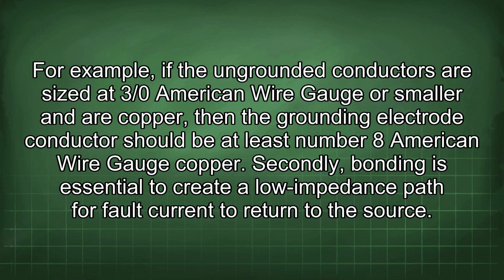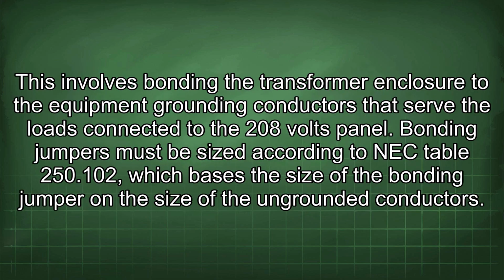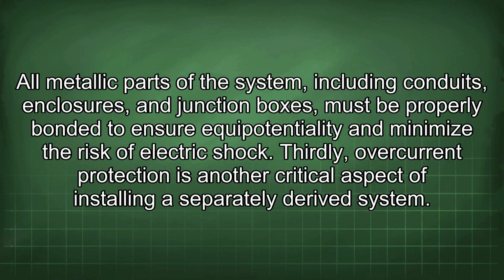Secondly, bonding is essential to create a low impedance path for fault current to return to the source. This involves bonding the transformer enclosure to the equipment grounding conductors that serve the loads connected to the 208 volts panel. Bonding jumpers must be sized according to NEC table 250.102, which bases the size of the bonding jumper on the size of the ungrounded conductors. All metallic parts of the system, including conduits, enclosures, and junction boxes, must be properly bonded to ensure equipotentiality and minimize the risk of electric shock.